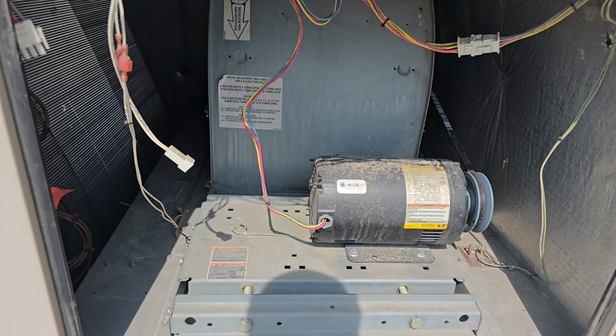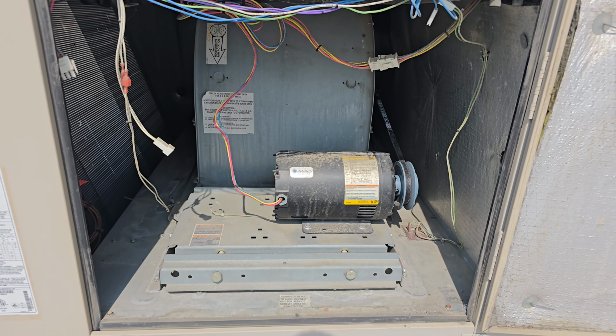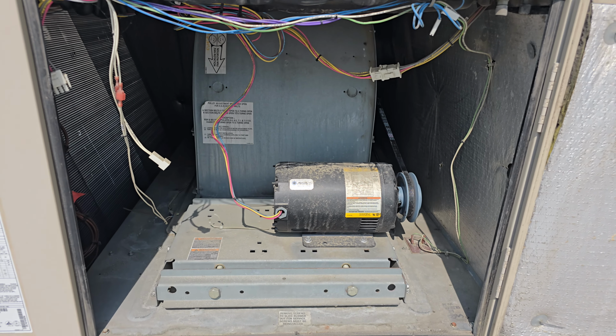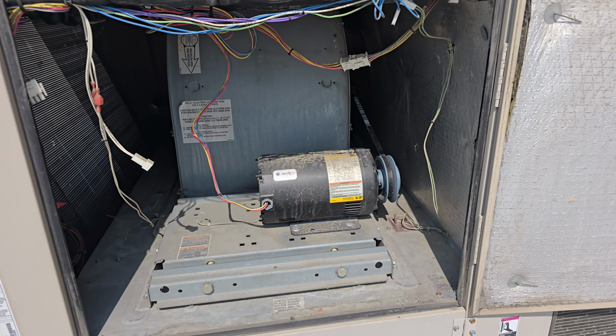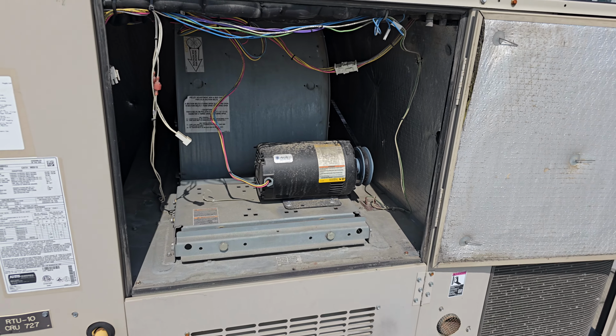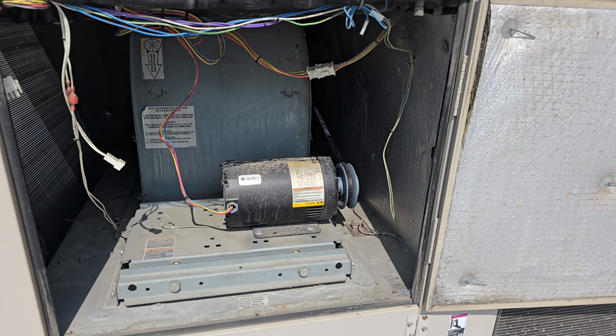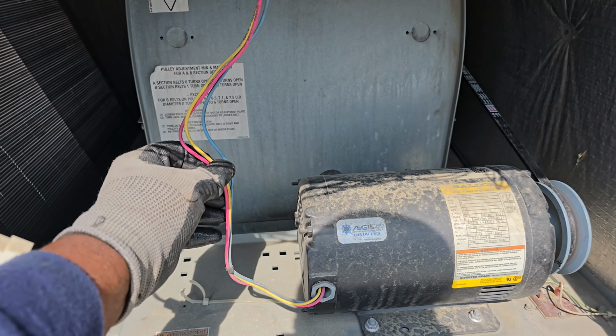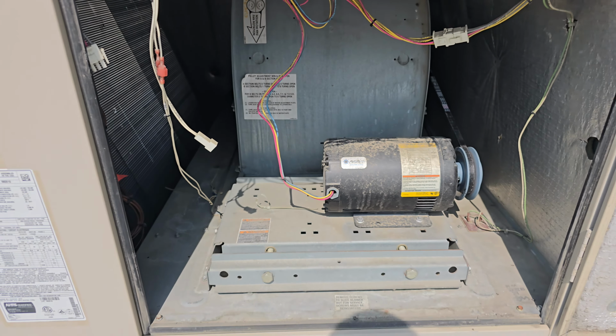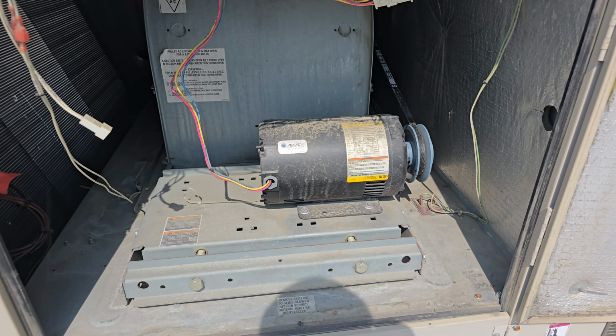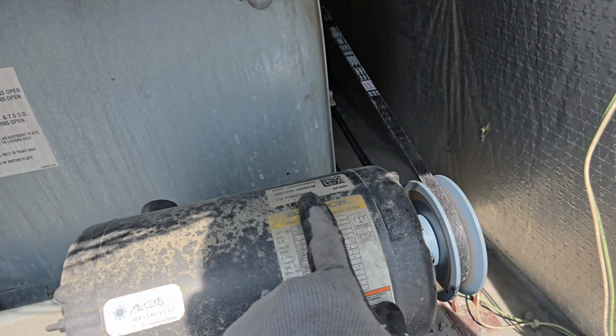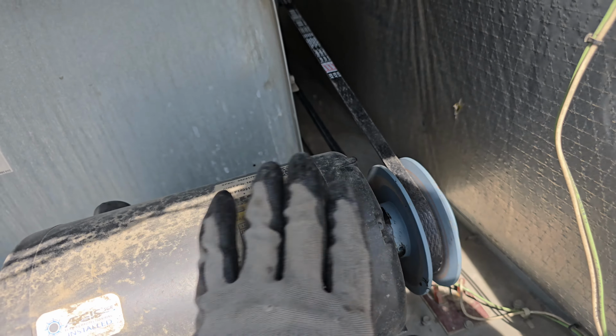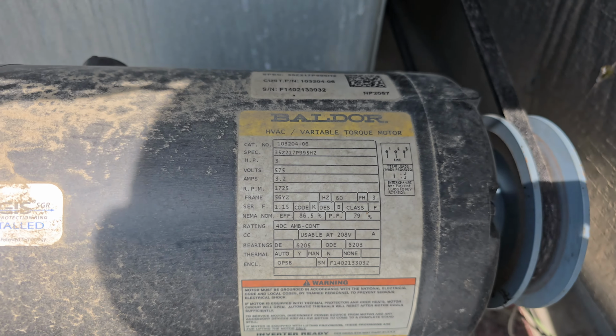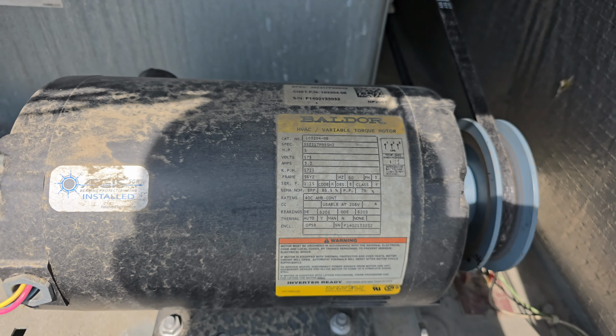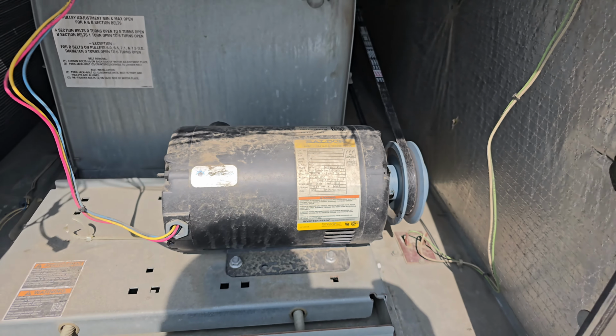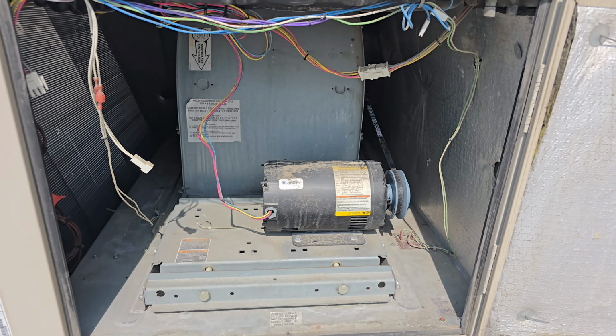Okay, and then please, if you have any question, put it below. I will try to respond to that. So after all of this is done, and when the unit comes back on, please take your amps reading. Put your amps meter in here or in there, and see if it's taking too much amps. The motor information is out here, and all the amperage are out here. If it is pulling too much amps or not good enough, you can always work on that.